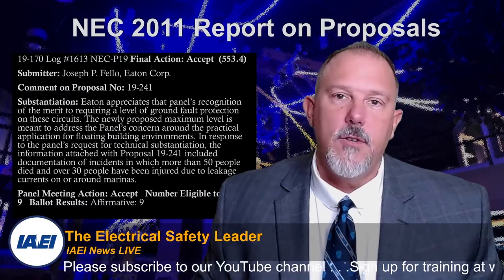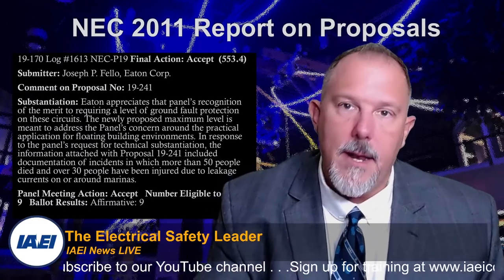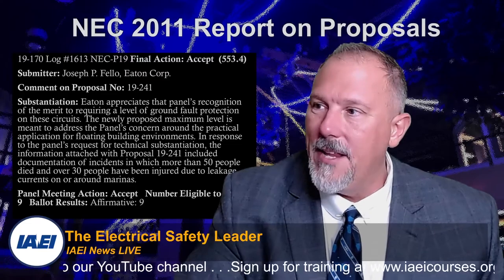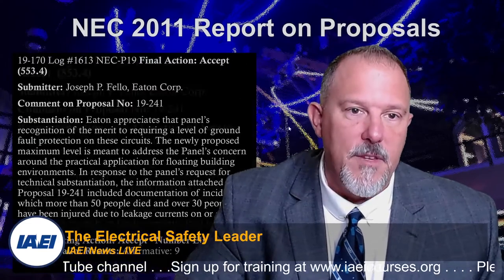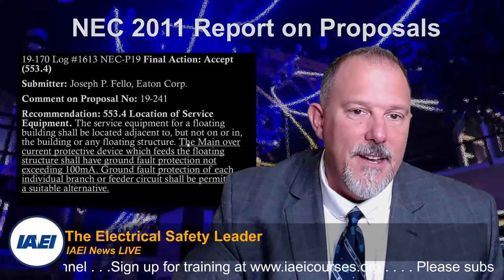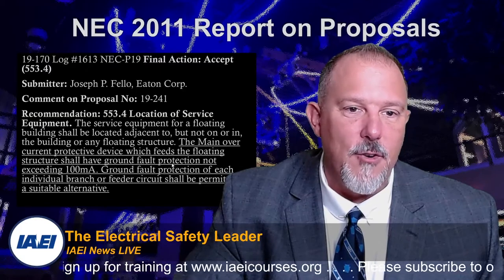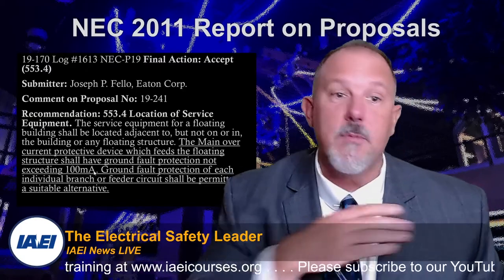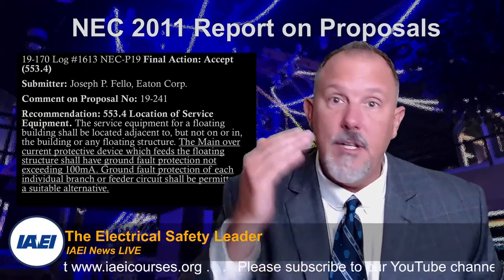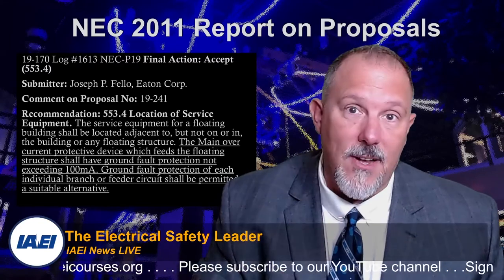They were concerned. There were claims that no products existed because nobody makes a 100 milliamp device, because it says the main overcurrent protective device shall have ground fault protection not exceeding 100 milliamps. Many people misread that and said you need a 100 milliamp device, and that's not the case.